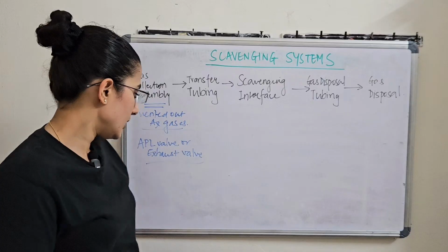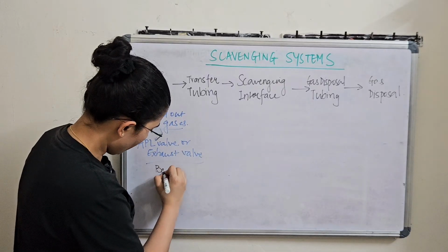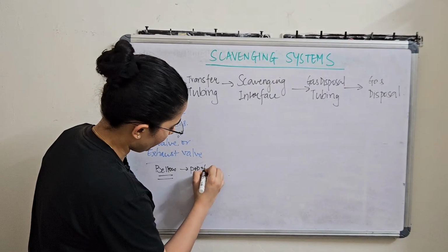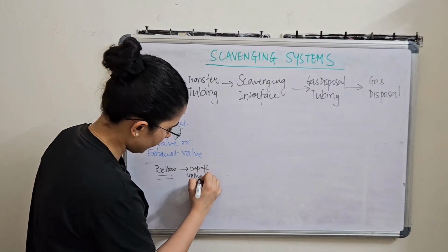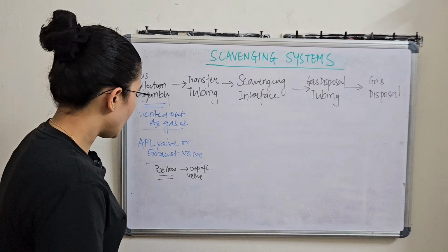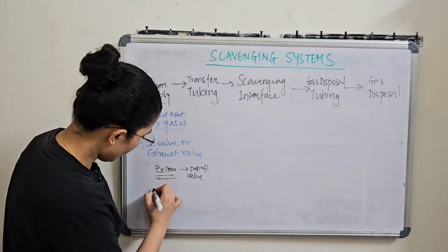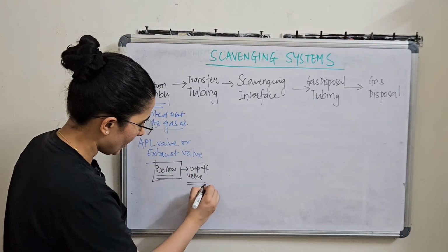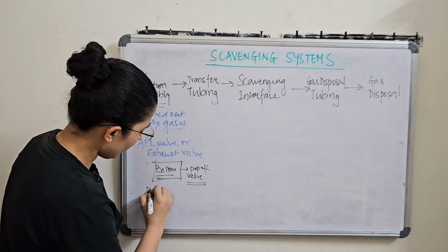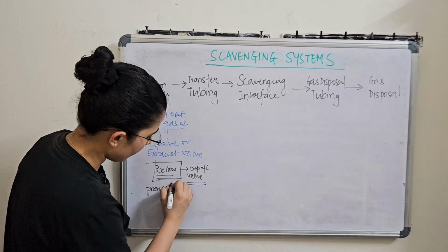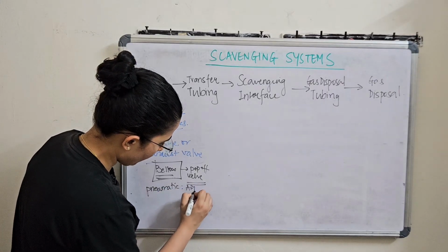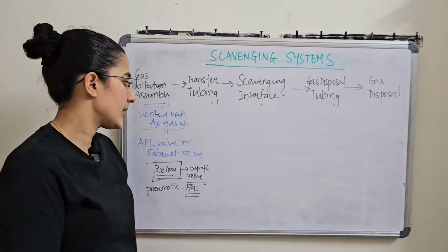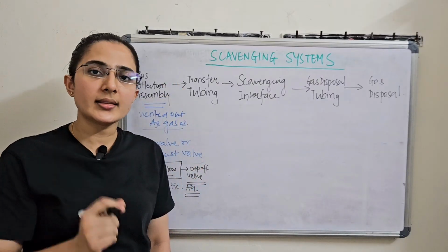So in case of a bellows type of ventilator, there is a pop-off valve that will be collecting these vented gases. Whereas in case of a pneumatic type of ventilator, we have an APL valve with minor holes that will be venting out these gases. So this is the gas collection assembly.